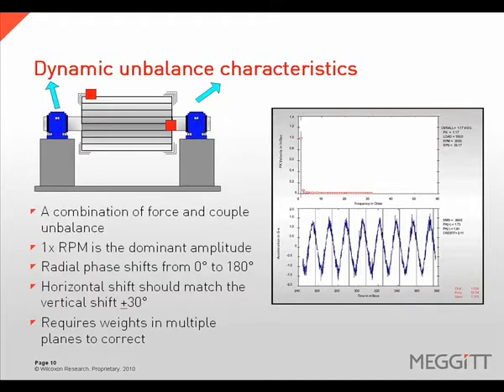Dynamic unbalance is a combination of force unbalance and couple unbalance. The dominant vibration amplitudes will occur at 1 times rotational speed. Radial phase readings will be unsteady from 0 to 180 degrees, and the horizontal phase shift should match the vertical phase shift. Dynamic unbalance will require a multi-plane balance weight placement to correct.